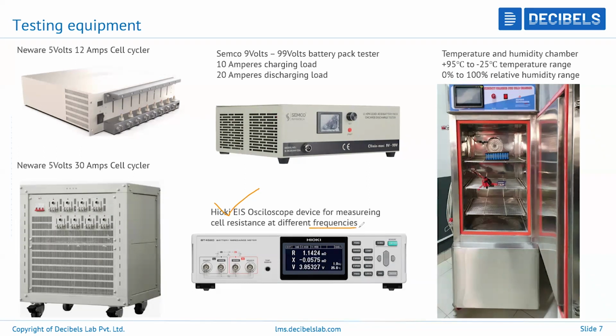So the current will be varied at small frequencies like 0.01 hertz to very high frequencies like 35 kilohertz. The current will be fluctuated in this frequency range, and from there you see how the resistance behaves, and you get the complete internal resistance characteristics. This is in terms of what is called ACIR, alternating current internal resistance. So it's AC current that is passed through the cell.